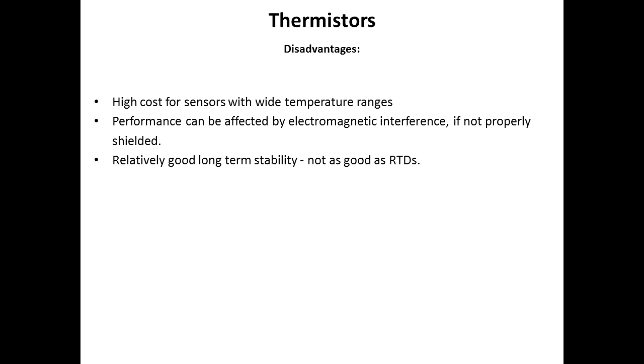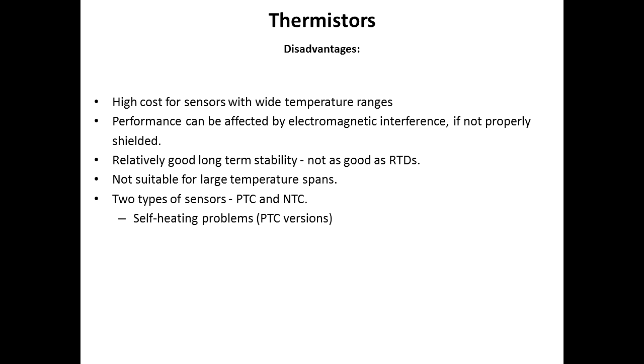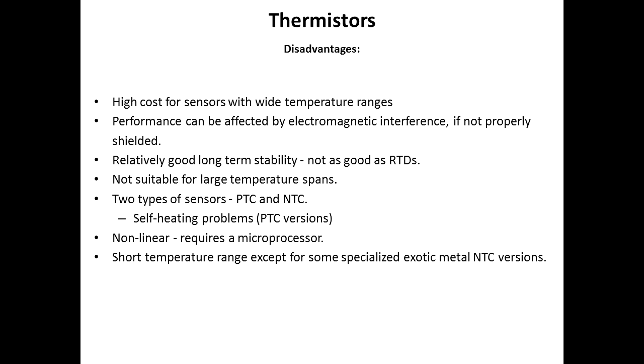Long-term stability is good, not as good as RTDs, much better than thermocouples. Not suitable for large temperature spans. We don't use PTCs because of self-heating issues. Non-linear, requires a microprocessor. Most thermistor sensors use a table lookup system where they'll have a little guy in the thermometer reading his book. He gets a resistance reading, he looks in his book to see what the temperature is, and displays that. So it's got to have a lot of memory if you're using a thermistor. Short temperature range except for specialized exotic metal versions. Poor interchangeability. Since there are not a lot of standardized curves, you can't interchange with other instrumentation very easily.